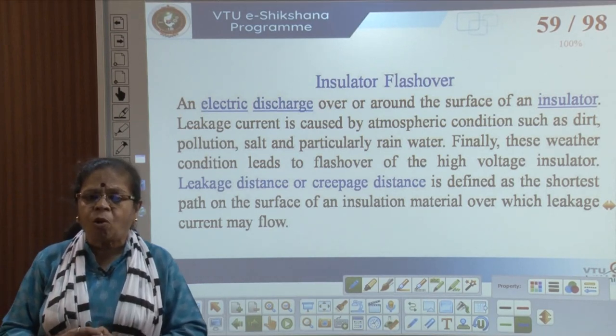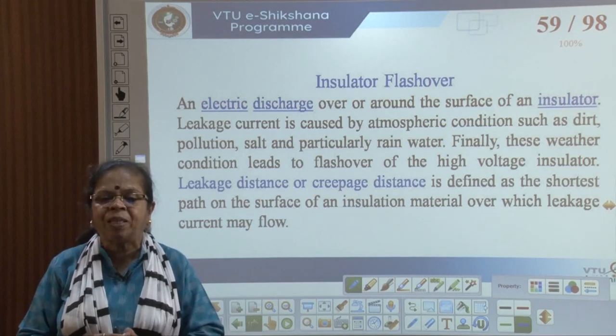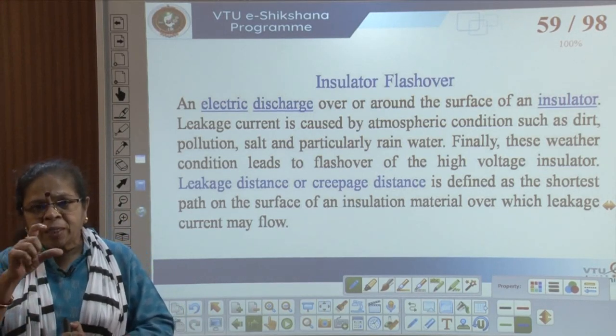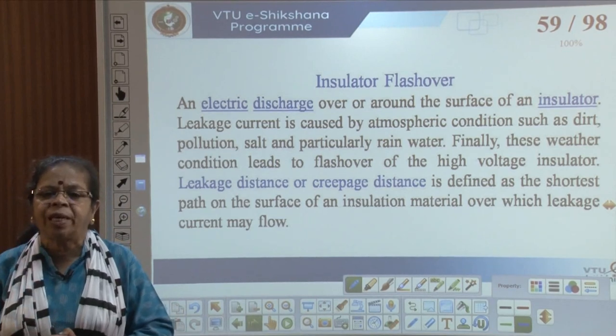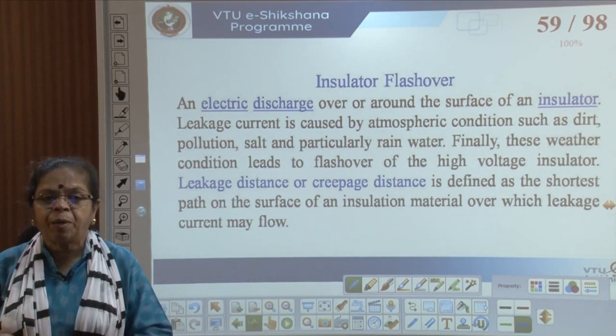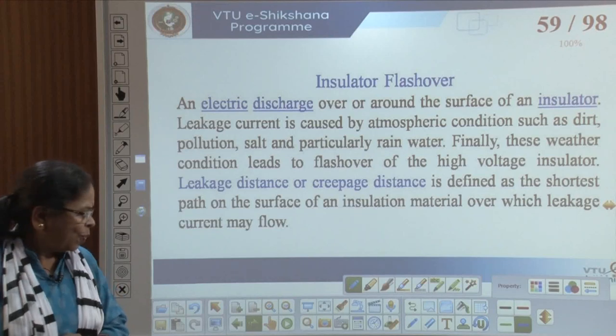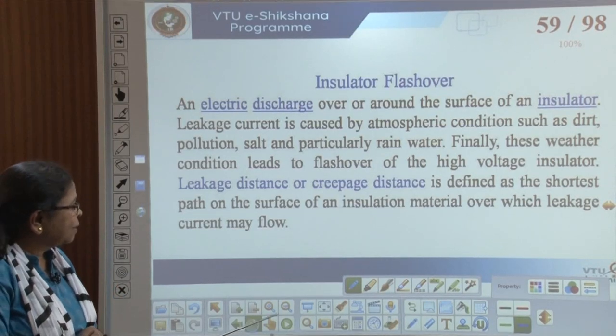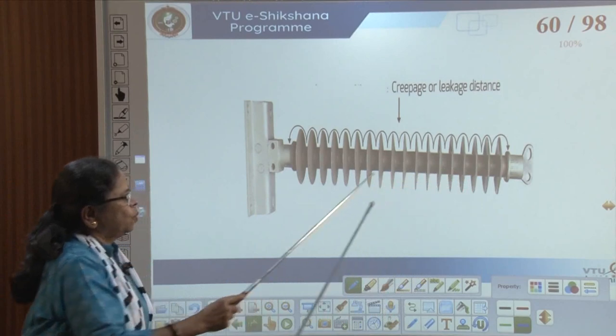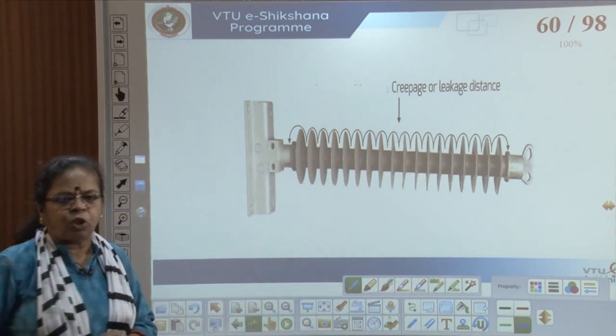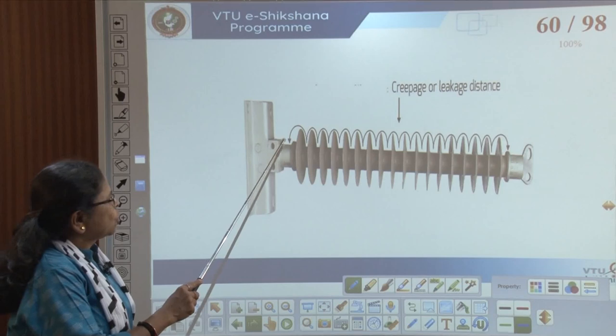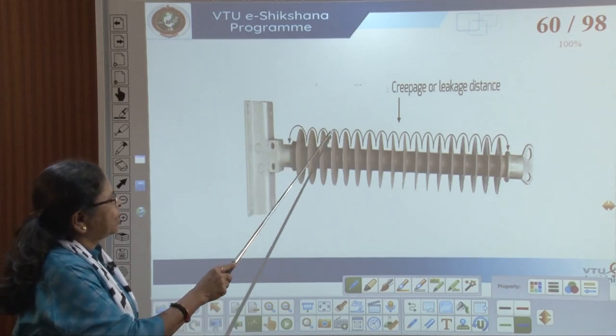We define the leakage distance or creepage distance as the shortest path on the surface of an insulation over which leakage current may flow. In a suspension insulator with many discs, the leakage current can flow along the disc surfaces.